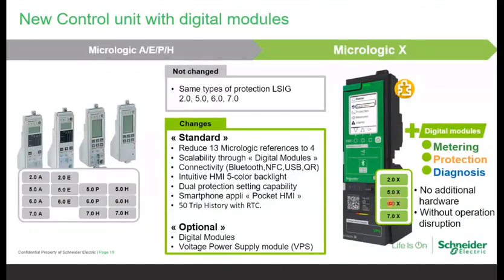so that if you have a 6X release and at any given point of time you want to upgrade your breaker, let's take again the same example. If you want a reverse active power protection, you have to go to the Go Digital website, or you have to call our service person. He will download just a particular digital module called reverse active power protection. Even if your breaker is under operation, if your breaker is on, still you can upgrade the protection of your breaker by using the digital module, and you have to pay just a few bucks for those digital modules.